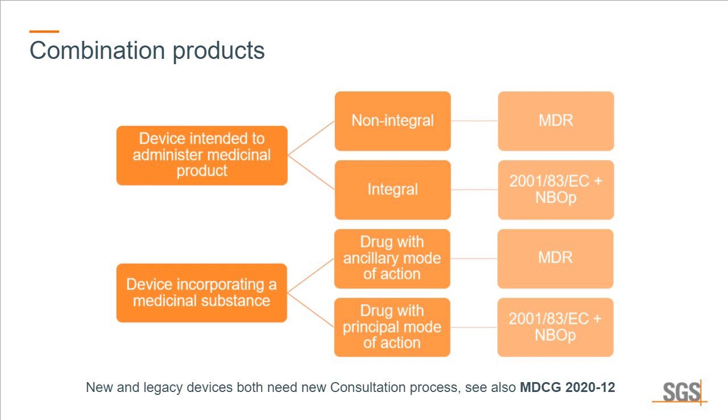But in order to put that product on the market, the regulators may ask that for the syringe portion, the notified body should give an opinion to the manufacturer whether the syringe fulfills the general safety and performance requirements of the MDR as well. So just be mindful that the pathways might be different in this case.